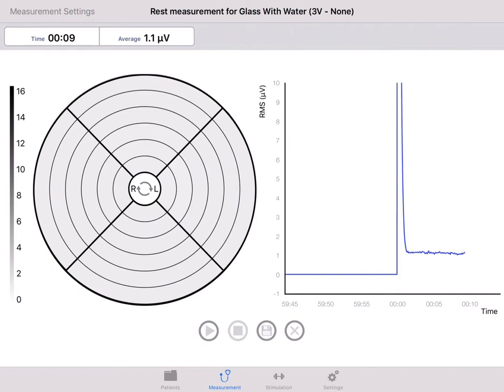When pressing the cross button, no measurement details are saved. The system will not ask whether or not to save the measurement; it will be lost, and you will be redirected to the measurement settings menu.